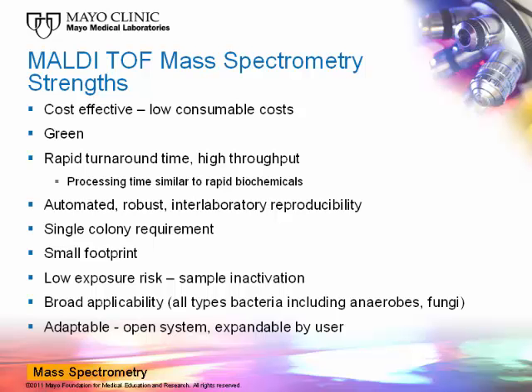In summary, MALDI-TOF mass spectrometry is automated, does not require specific expertise in mass spectrometry, and has a rapid turnaround time and high throughput capability. It only requires a single colony and is associated with a low exposure risk due to sample inactivation. This approach is cost-effective, has demonstrated high interlaboratory reproducibility, and has broad applicability, covering all types of bacteria including anaerobes and fungi. The system is open and adaptable by the user.